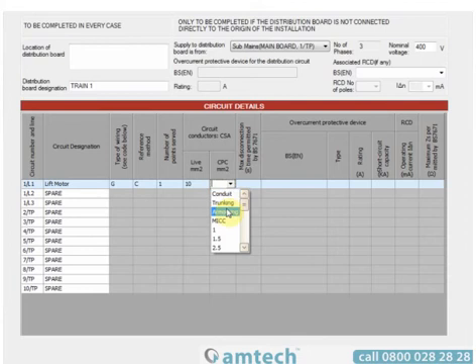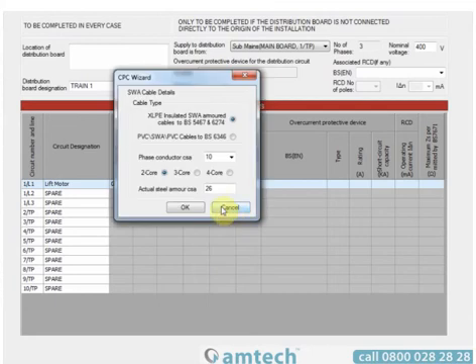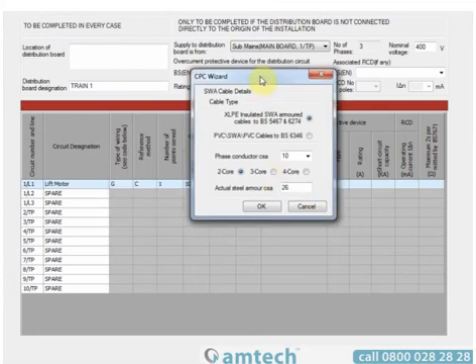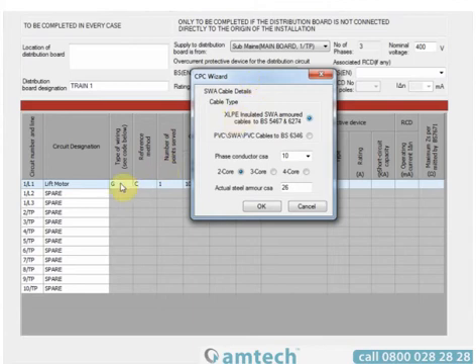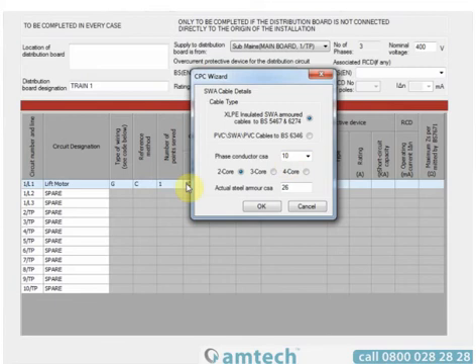In this case we're using armoring as designated in our type of wiring section, so if I were to select the armoring option in the drop-down it would bring up the CPC wizard. The CPC wizard self-populates with values if they've already been entered — in this case it's selected XLPE because we've selected a thermosetting cable in our type of wiring.